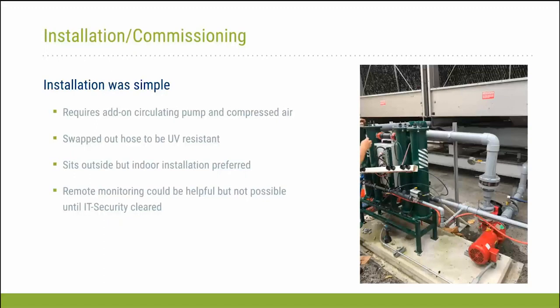The unit itself seems to be holding up pretty well outdoors, with no cover on it. Part of me wants to say, if I was doing this at another facility, I'd like to see it inside, but you do have the issue of it getting kind of messy to do the cleaning because of the water, and the material accumulation can be a little bit messy. So there's a little bit of a balance there. Outside, there's certainly a lot of room to work around in this particular location, and so far it seems to be working outside without any really accelerated corrosion. Understand that this location is near the coast, you've got salt air, and it still seems to be holding up well.